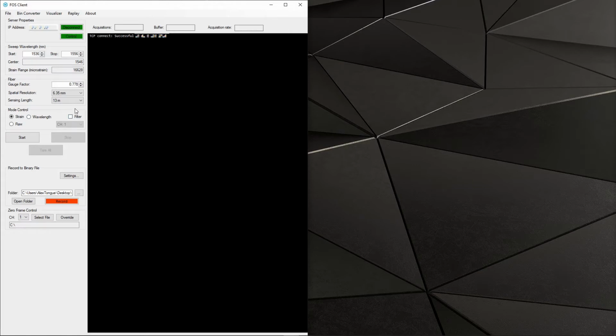These outlier points can be caused by some installation faults. When you install fiber optic sensors for strain measurement, you tack the fiber in place using spot glue techniques before applying a continuous line of adhesive. At those spot glue locations, you can induce significant gradients if you apply tension between the tack points. That tension and high gradient between the tack points can cause local points of high noise, which is easily mitigated through the filter. Although it is important to note that using best installation practices, these points are easily avoided in the first place, and you do not have to use the filter. Sensuron recommends turning this filter off by default and only using it if it's absolutely necessary.